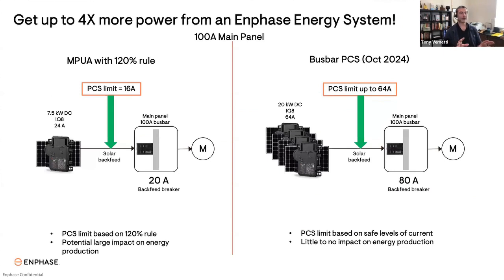So to make it really crystal clear, the differences between the current version and the upcoming version, I've got them side by side here. So we say with the new version of PCS, you can have up to 4 times more power from an Enphase system. So here we have an example again with a 100 amp panel. On the left, we have the 120% rule, where there's a hard limit of 16 amps of backfeed current. In this example, the PV system is a little bit oversized at 7.5 kilowatts DC, which is rated at 24 amps. So basically on a sunny summer day, you've got high irradiance and the power output of this PV system would likely get clipped or curtailed, and the homeowner is going to miss out on potential savings.